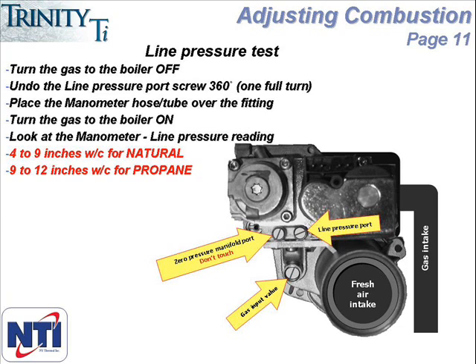To perform the line pressure test, start by turning off all the gas coming into the boiler. When you look at the gas valve from the right-hand side of the unit, you'll see three adjustment screws. The one on the top right is the line pressure port. Loosen it by turning the screw one complete turn counter-clockwise.